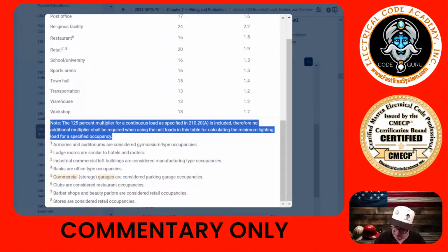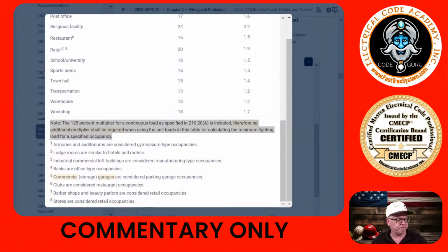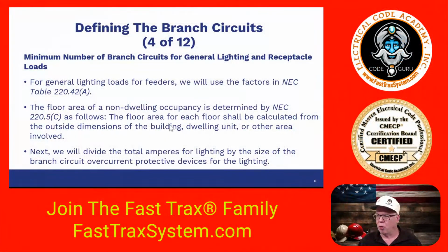So we write that down: 65,000 VA is our lighting load, already factored in, and we know what the loading is. All right, let's get back to the lesson. Once we do that, we'll know our value, so next you just divide it. We need to find out how many branch circuits.